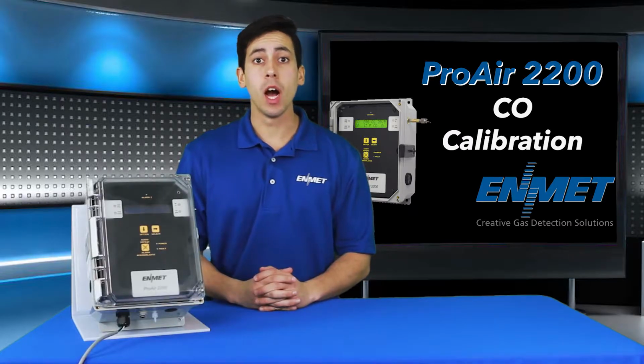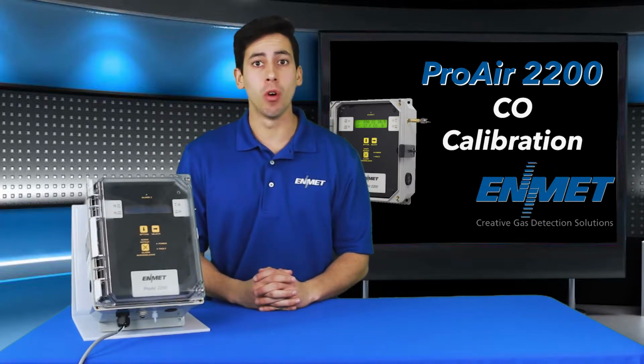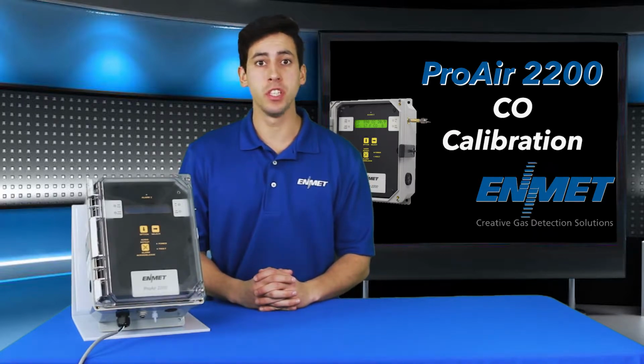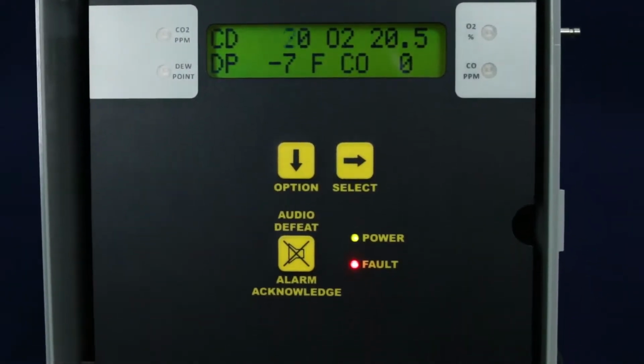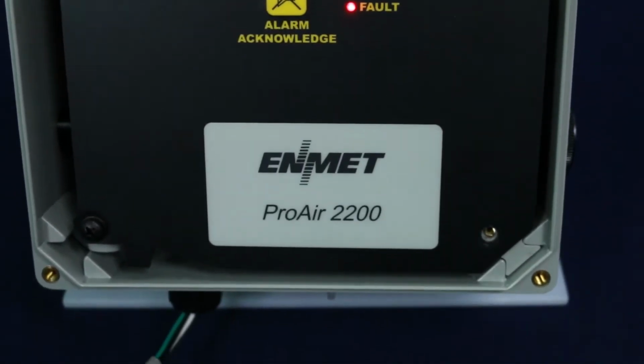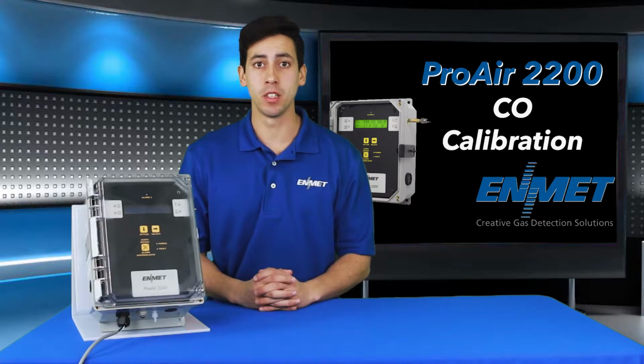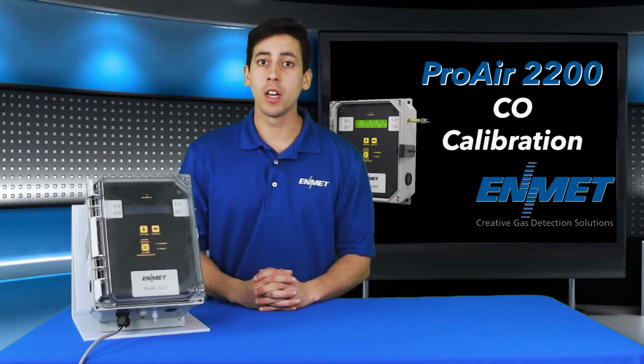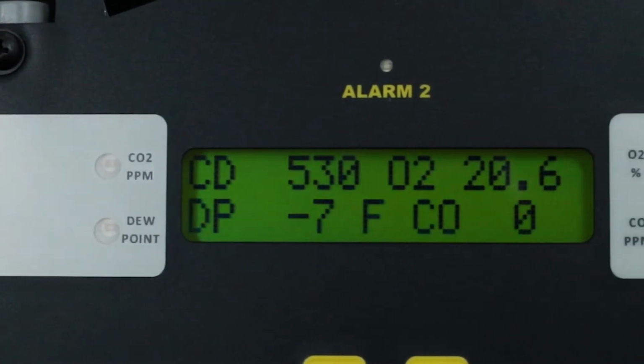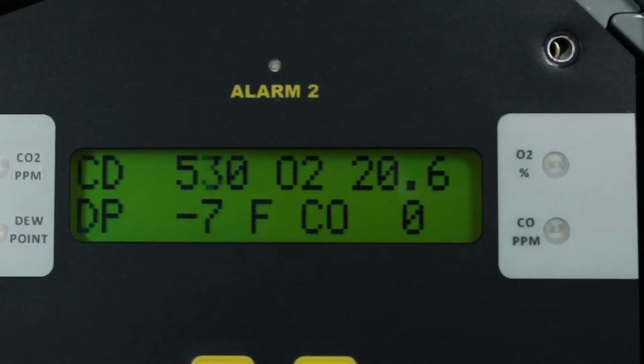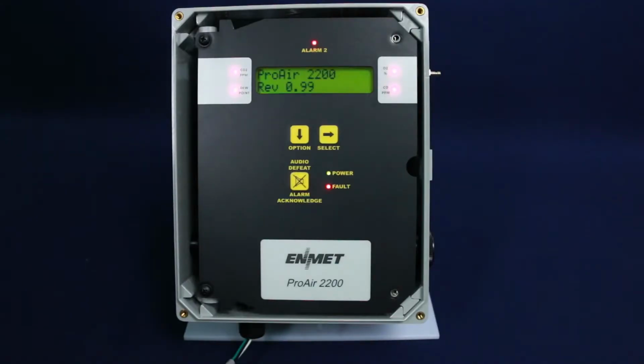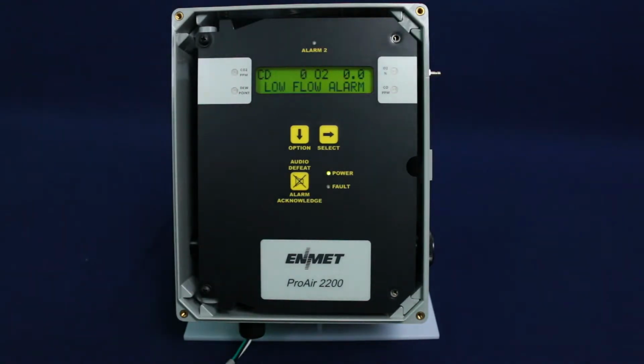In this video, I'll be walking you through how to perform a two-point calibration procedure for the CO channel of ENMET's ProAir 2200 compressed airline monitor. Before starting a calibration for the CO channel, you must supply air and power to the ProAir 2200 for at least 15 minutes, allowing the sensor to stabilize.